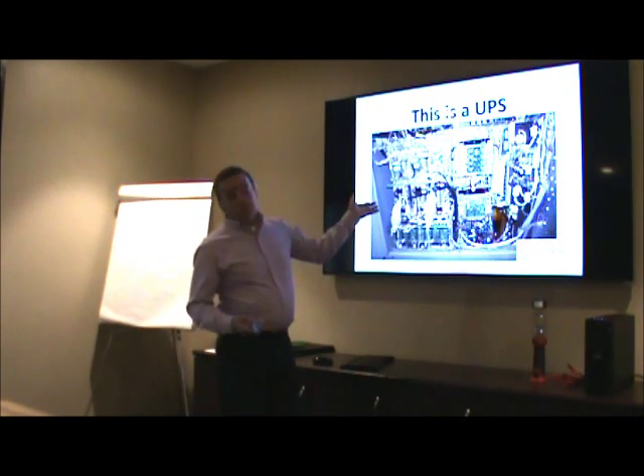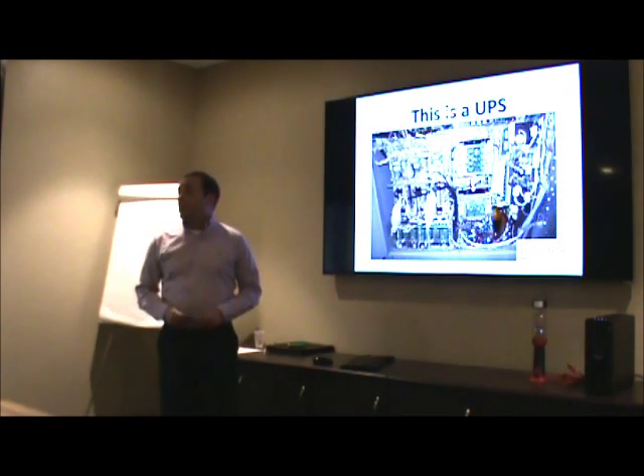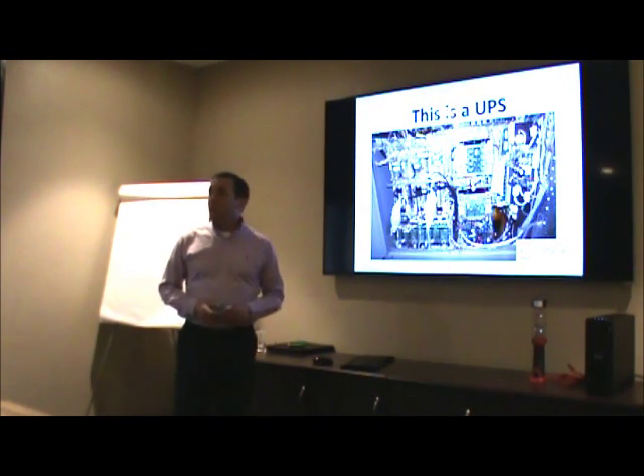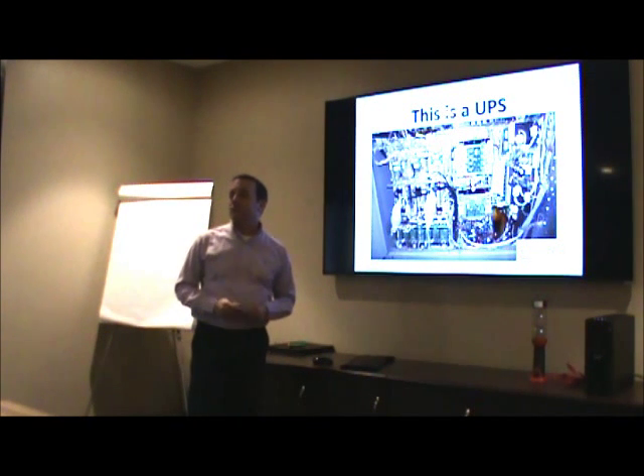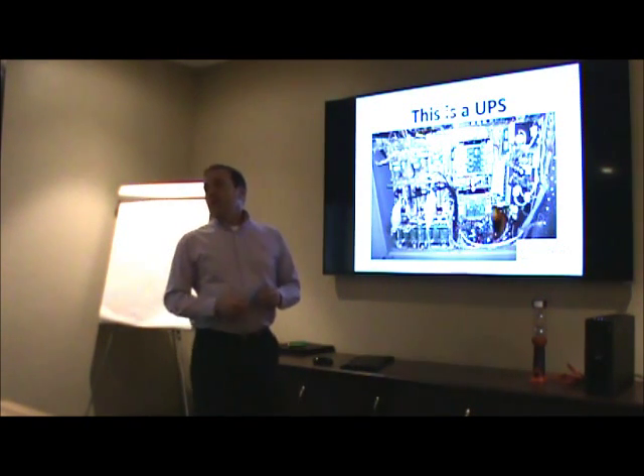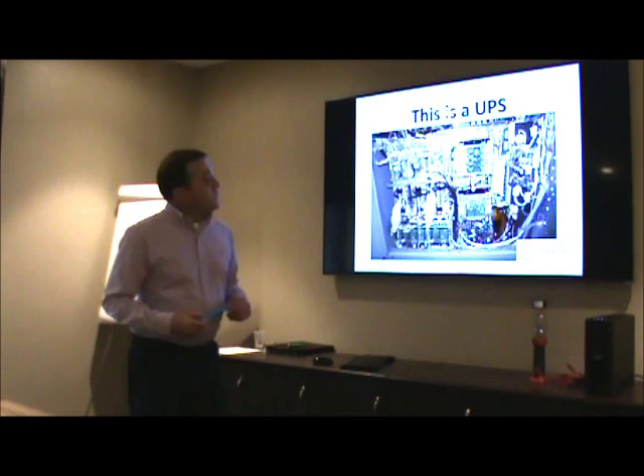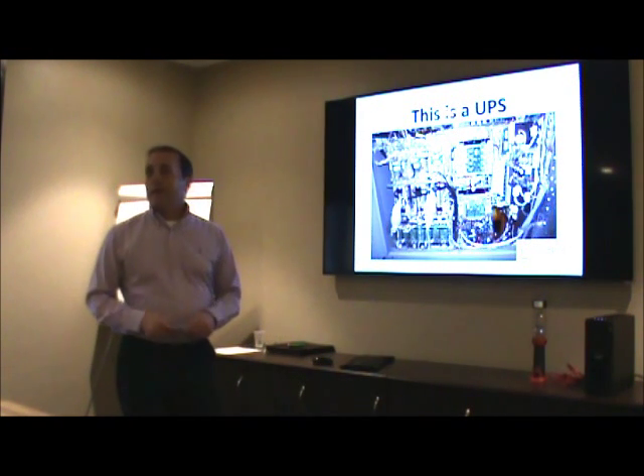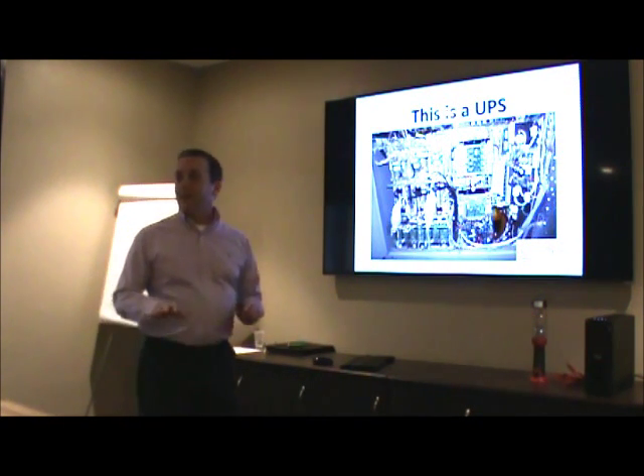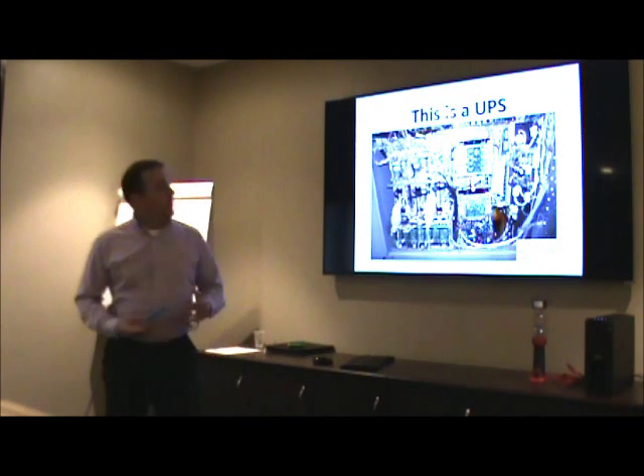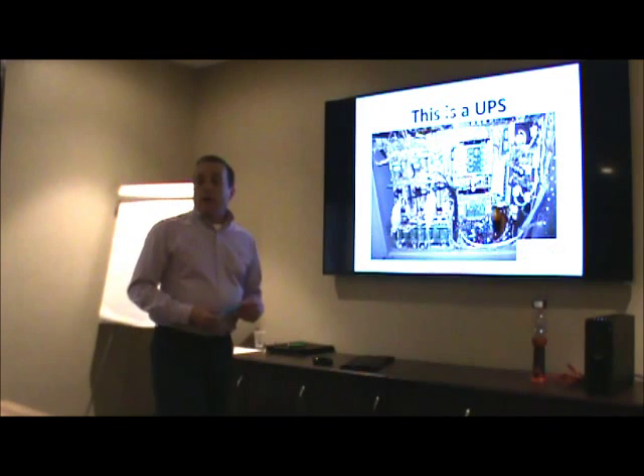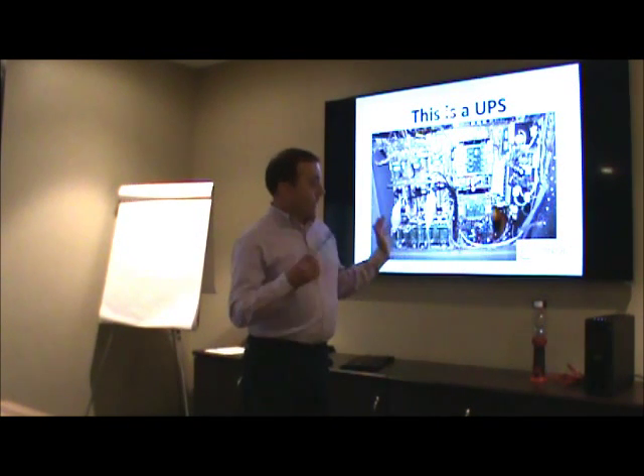This is typical of a UPS that we'll have in a rental department. This is about a 150 KVA UPS — when I say 150 KVA, it's basically 150,000 watts. KVA and KW ratings, we're not going to get into that today — it gets a little technical. A 150 KVA UPS is actually a 120 KW UPS.